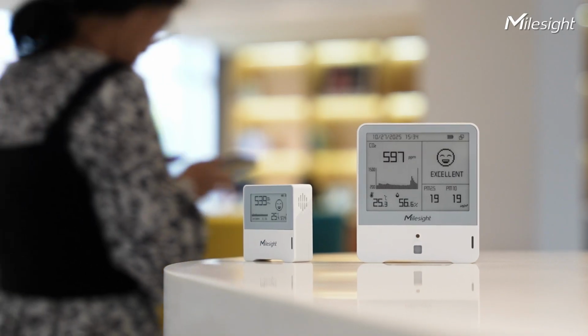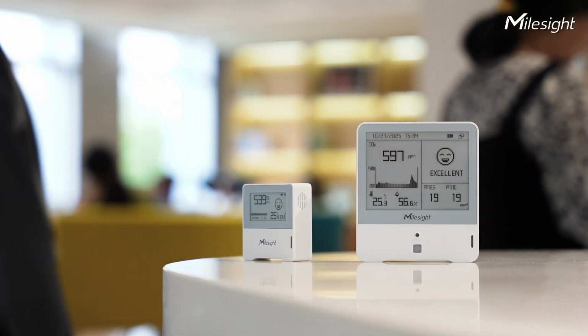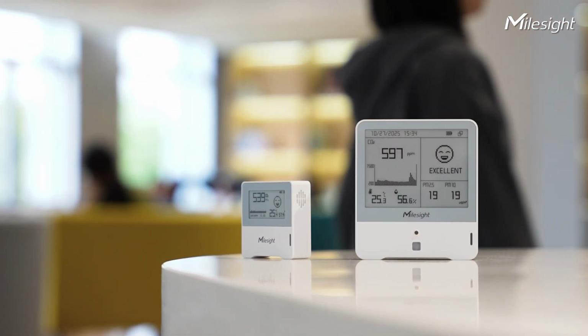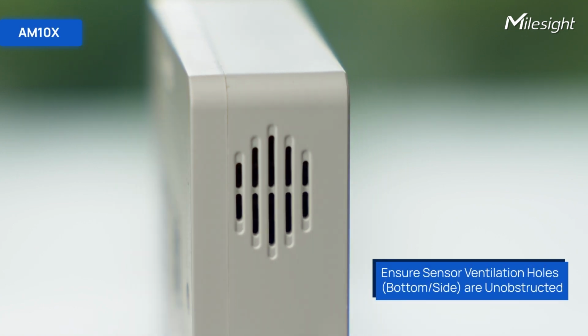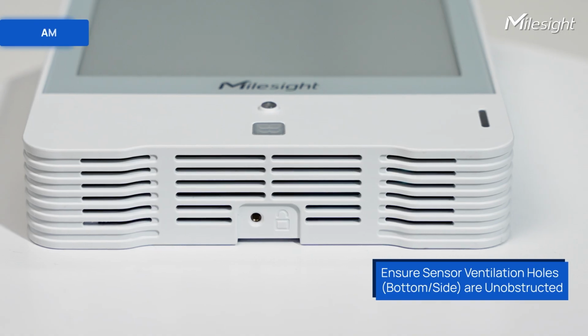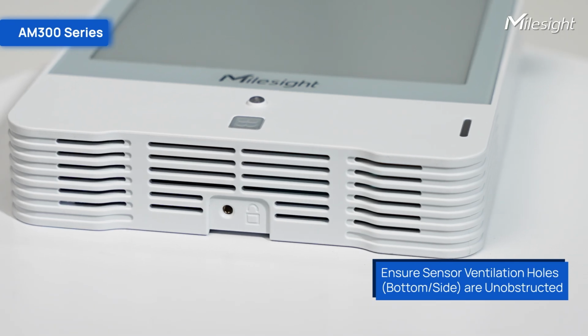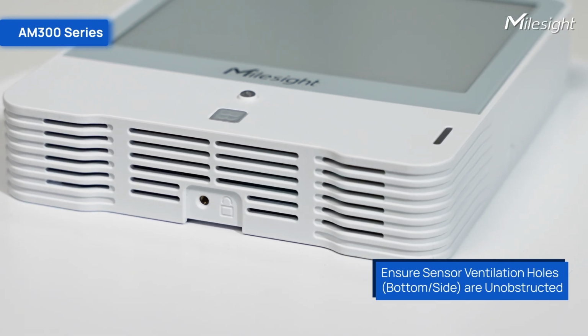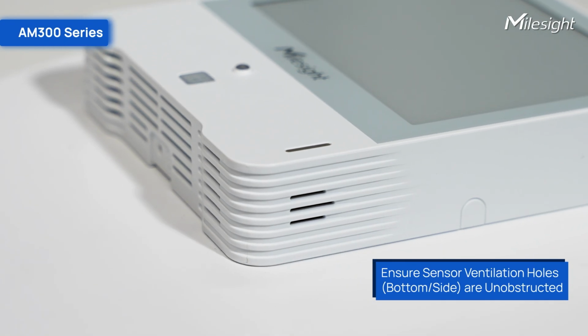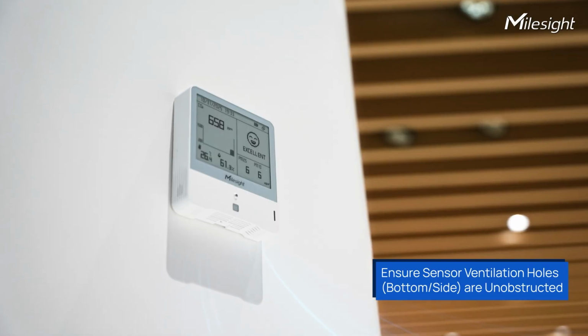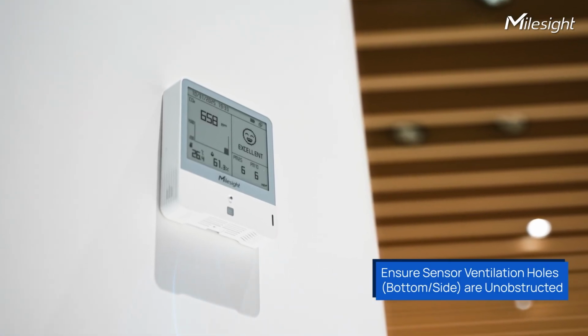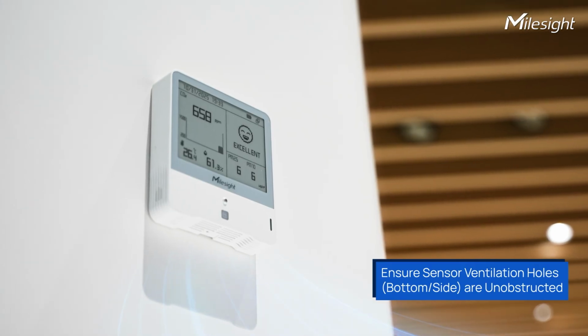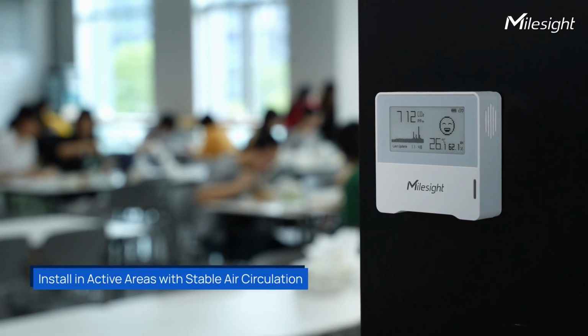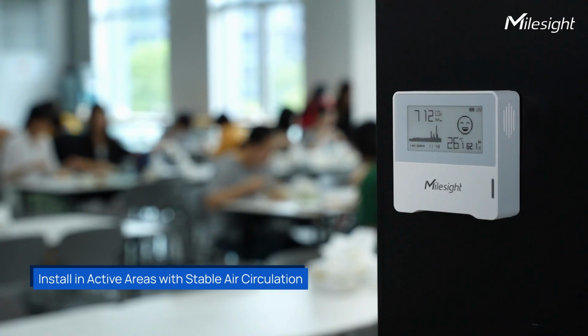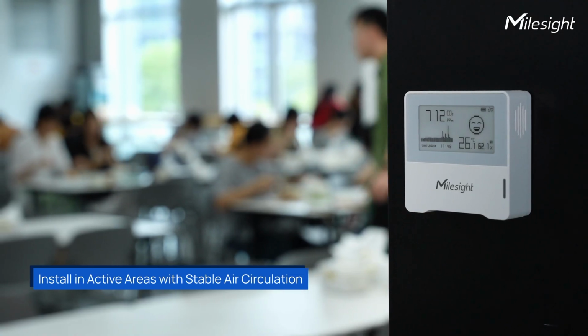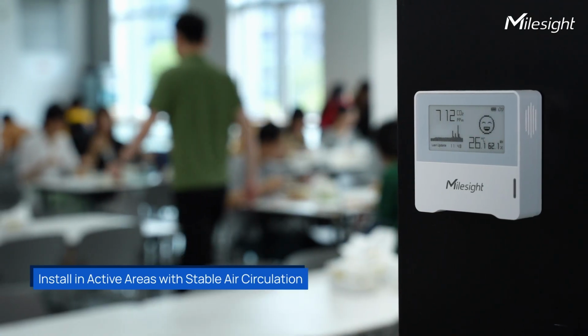Beyond placement and quantity, a key physical requirement is ensuring proper air access. Specifically, we should ensure the device's ventilation holes are not blocked. IAQ sensors usually have ventilation holes at the bottom or sides. During installation, ensure the holes are unobstructed, otherwise it will affect the accuracy of the data collected by the sensor. To accurately capture gas concentration in the space, the sensor should be installed in an area of the room where air circulation is relatively stable and there is human activity.